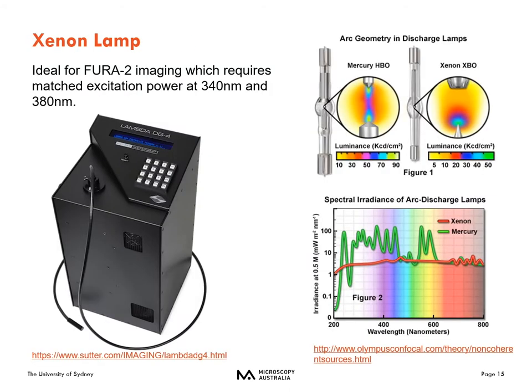Another common fluorescence light source is the xenon lamp. Its spectrum has far fewer peaks than the mercury lamp, which is particularly important for applications like FURA-2 imaging requiring matched excitation power at 340 and 380 nanometer excitation wavelengths. This lamp is also very temperature dependent, so it needs a long warm-up and cool-down time like the mercury lamp.